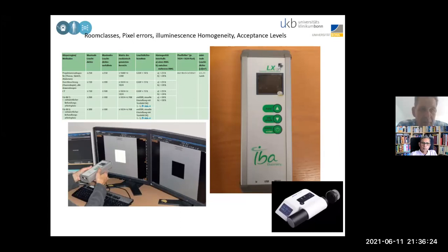In Germany, we really distinguish certain devices. Mammography monitors are not allowed to be situated in a room where the room class is higher than one. So prepare your rooms to watch the right image. So what else do we have to do? Semi-annually, check the minimum luminescence and maximum luminescence. We have to use the contrast from minimum to maximum. Then we have to check if the monitor is off. Then you check the luminescence curve. That is the curve I also said, the DICOM curve I already showed.